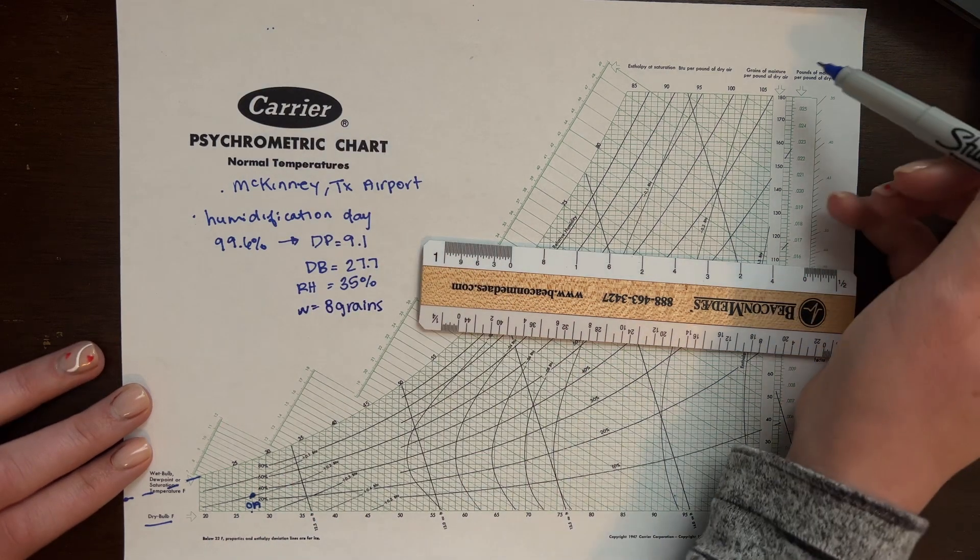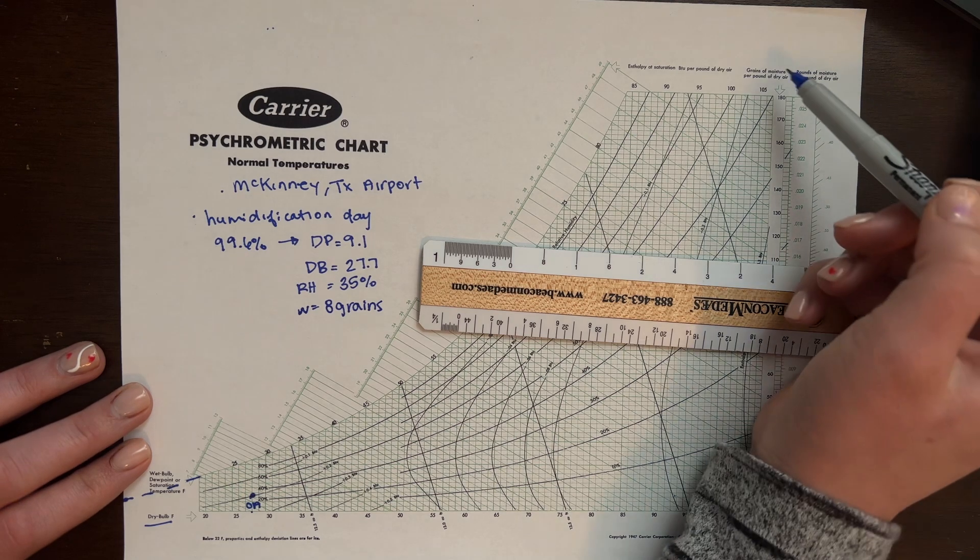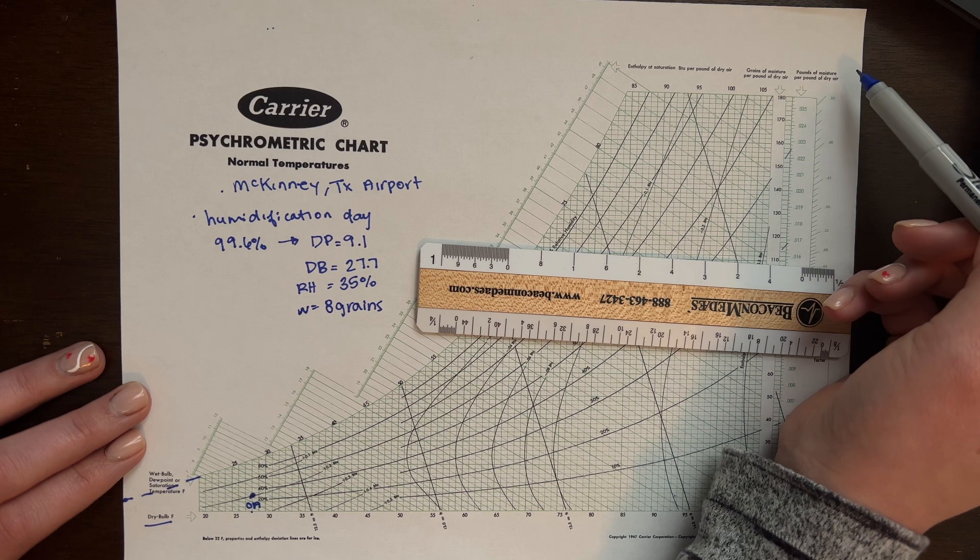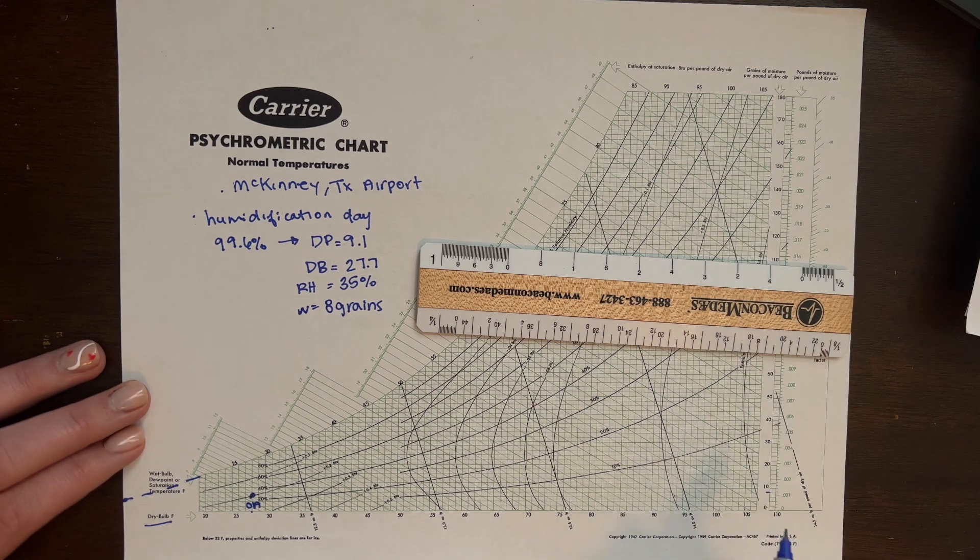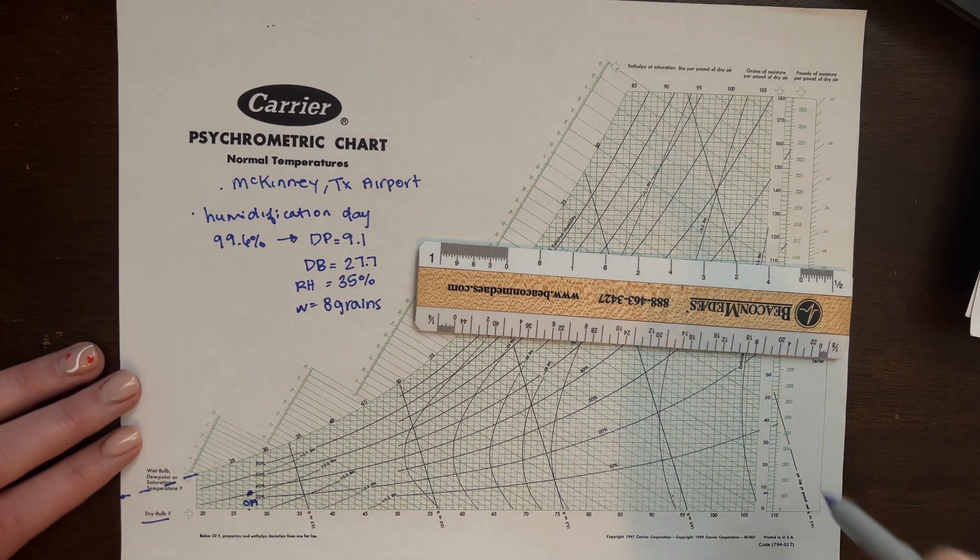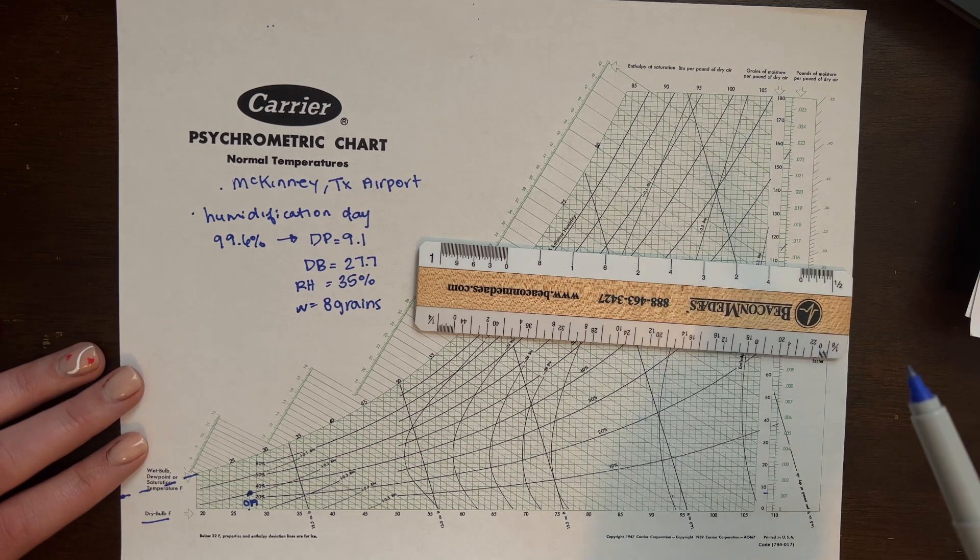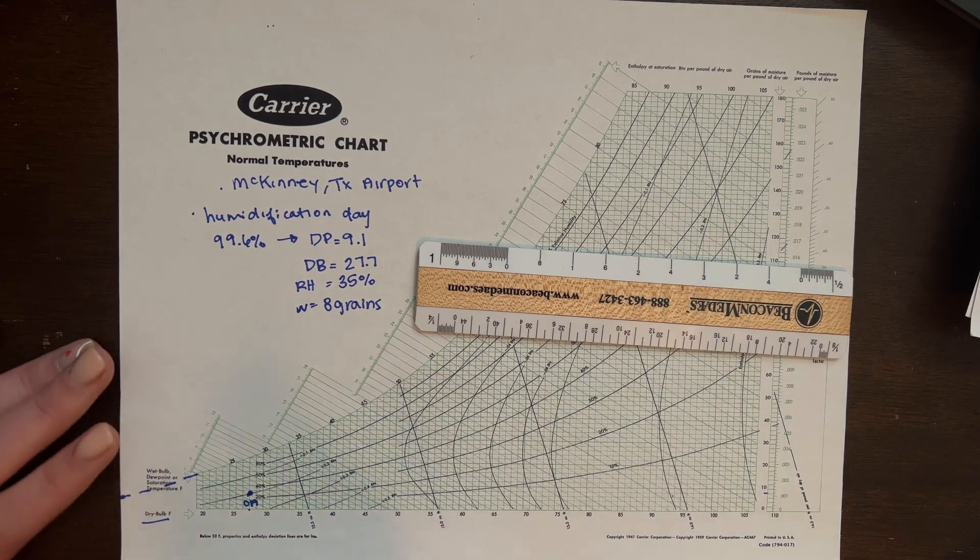You can see right here on our y-axis, we have the amount of moisture either in grains of moisture per pound of dry air or pounds of moisture per pound of dry air. I like using grains because it's a little easier to read on this graph. The conversion unit between the two is 7,000 grains equals one pound of moisture. So just something to note.